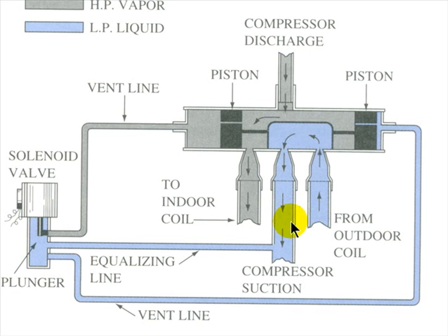Reversing valves, and I'm going to say something that's not totally true, but true 99.9% of the time, reversing valves don't go bad. I mean, the solenoids go bad, all that jazz, but the valves don't go bad because there are no moving parts. You have a slide inside here that's going to move a total of maybe an inch and a half. It's surrounded by Teflon, which gives it a nice flow, a nice movement. What is it that's going to go bad exactly? I mean, eventually, over time, if this thing is installed for 200 years, the friction from the movement of the refrigerant is going to ruin it, but that's not going to happen in the lifetime of the equipment.